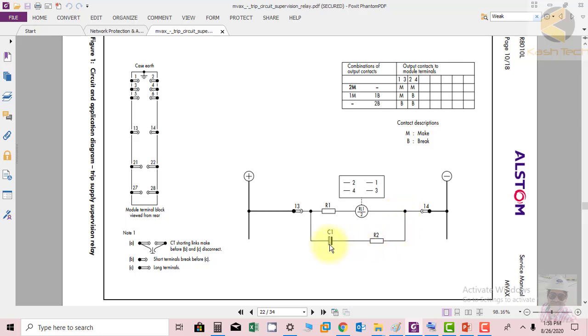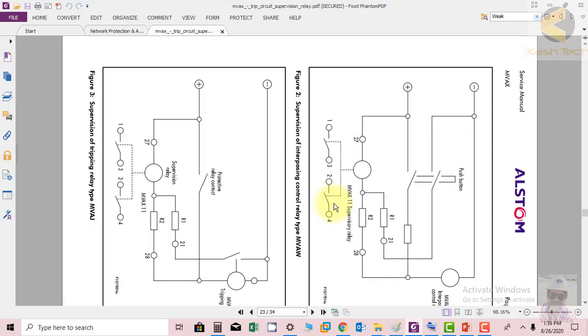The function of this, you have studied the time constant TC. So when, for example, there is no supply, this capacitor will provide the supply through this resistor R2 to this coil. So you can calculate the time constant through it. What is the function of this? In case of switching or during a transient dip, the MVAX should not operate unnecessarily, and it can provide a backup of 200 to 400 milliseconds. If there is a dip, this capacitor will supply the power to the coil to hold on. So this is the function. This is very important.